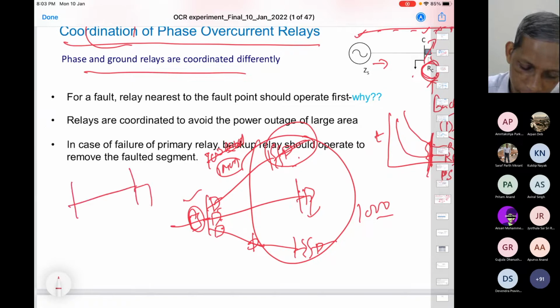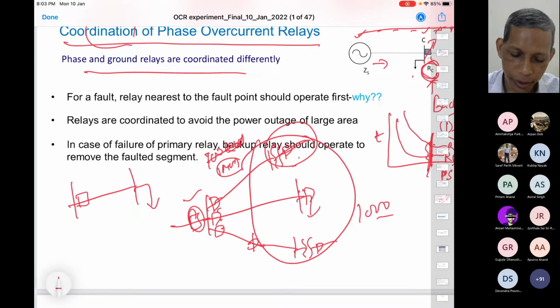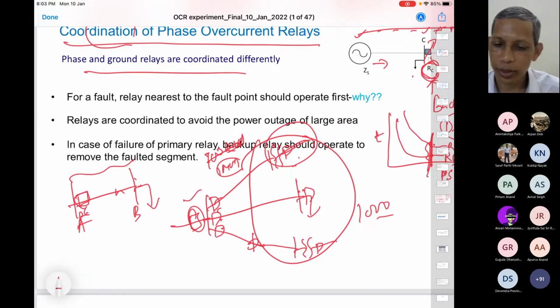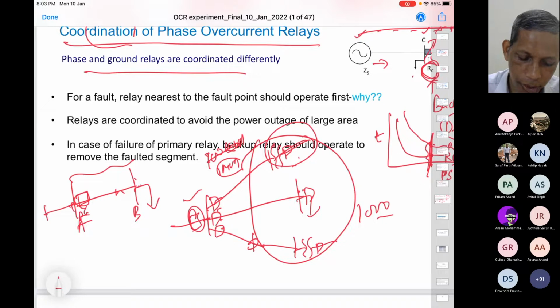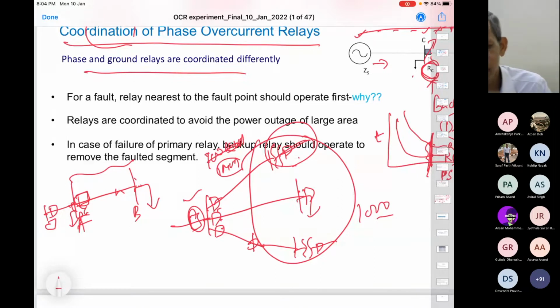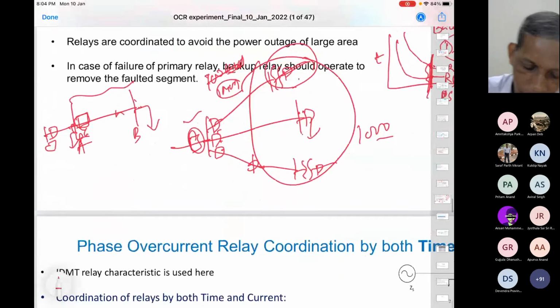If it is a radial system like this, you don't require a breaker here, you require a breaker here. You don't require a breaker anywhere else. And the fault can happen anywhere up to this direction. This is bus A, this is bus B, and this is a line. So you put a breaker here, then a relay here, and that is sufficient. When you go to the upstream side, again if you load here or a bunch of loads here, then you require a breaker here. And how do you decide whether the investment is worthy or not? That you decide. But your question is another valid question.